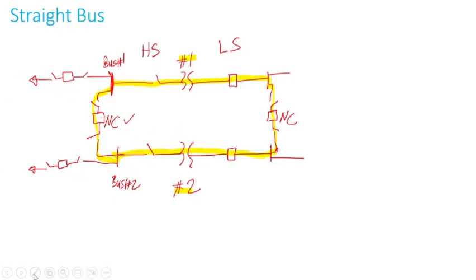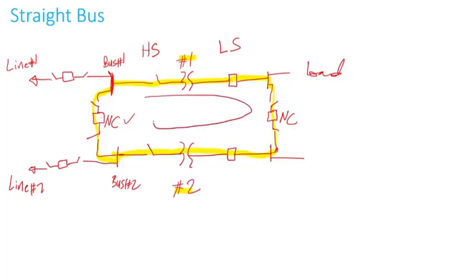Let's assume this is a line or feeder number one — you can have multiple, but for simplicity I'm showing two. Line one is energized at bus one, line two is energized at bus two. The low side goes to the load. If transformer one and transformer two are not on the same tap or don't have the same turns ratio, you could have circulating current, which is trapped in the loop formed by the high side and low side of the transformers.